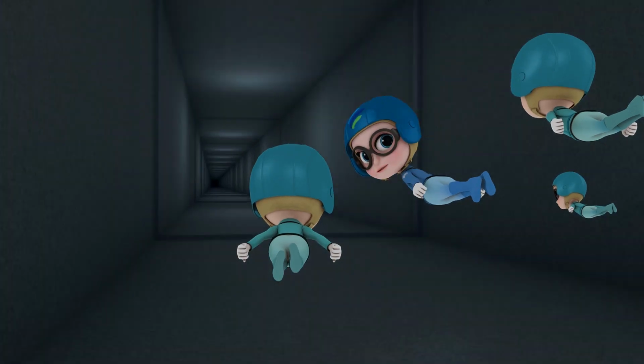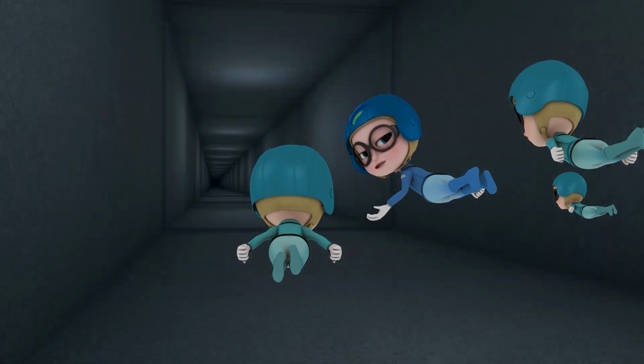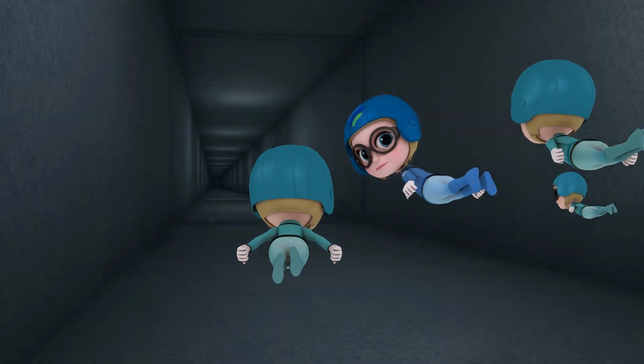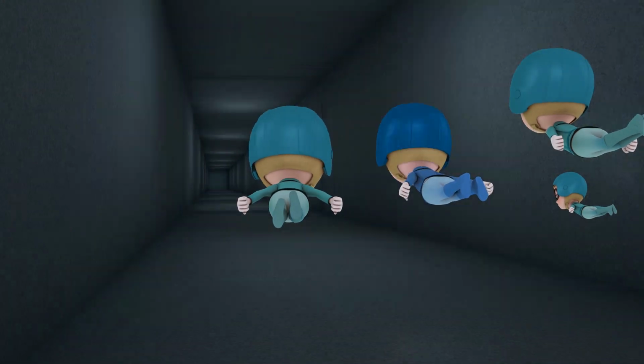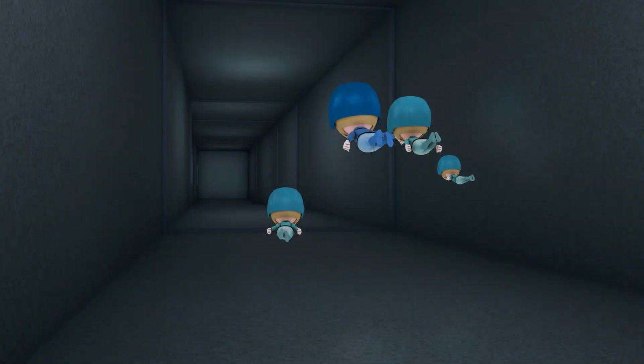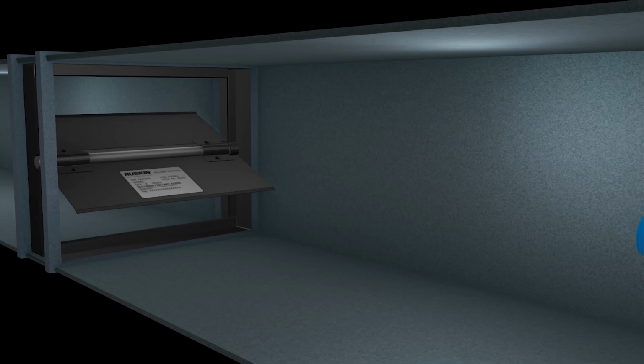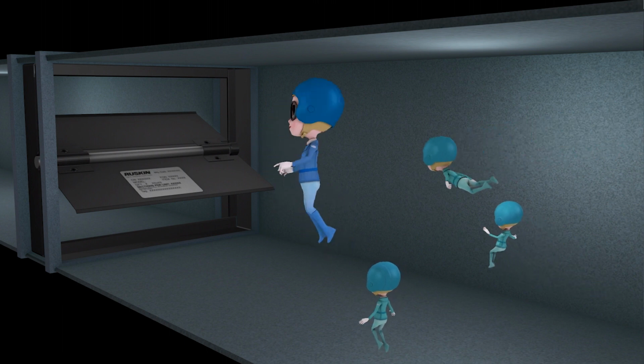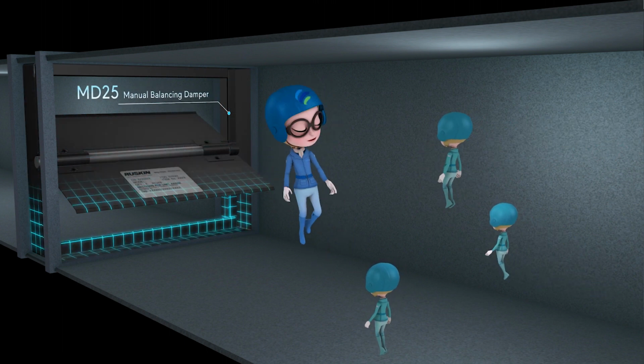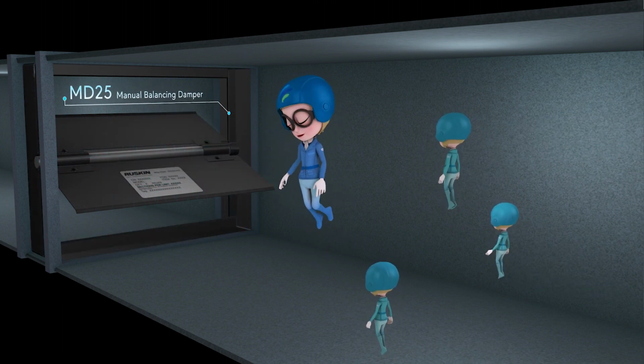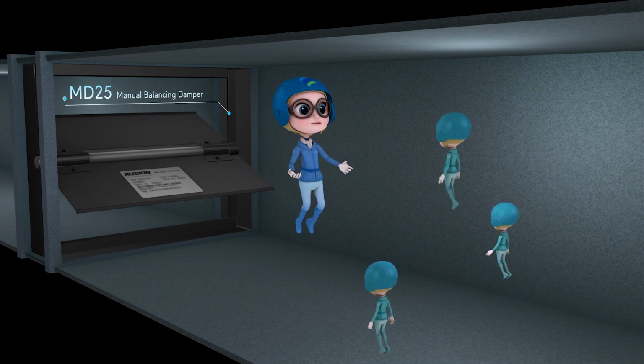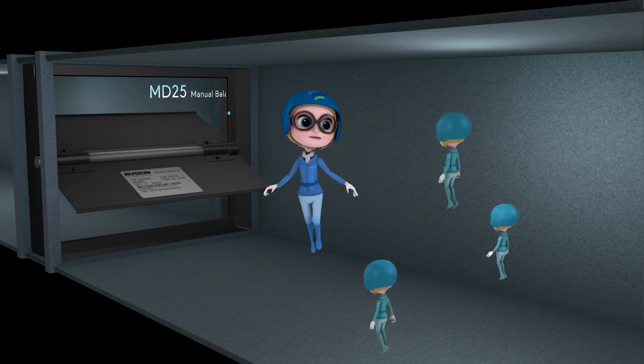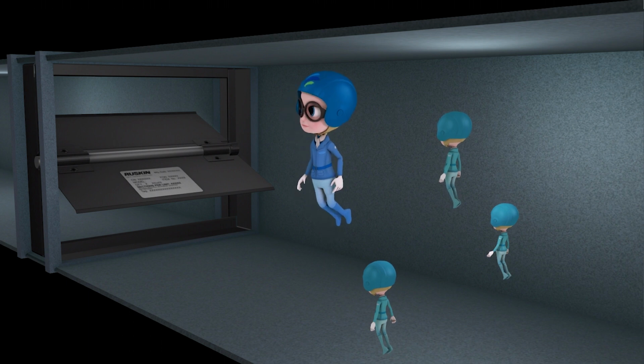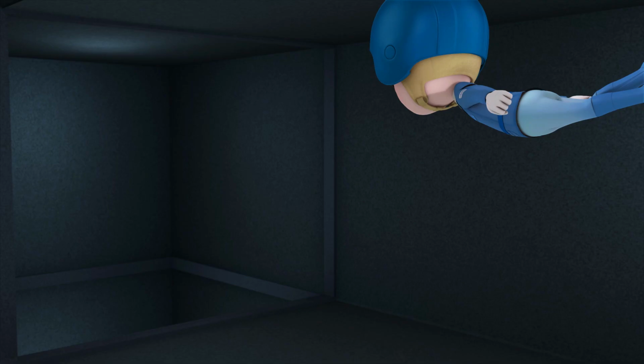Team, we're almost to our destination. Once we pass through that manual balancing damper, we will have arrived in the space that needed fresh air. Manual balancing dampers are placed at each point where a main duct splits off into separate ducts to feed individual spaces. They help direct how much air flows to a space to keep the comfort level at the set points.